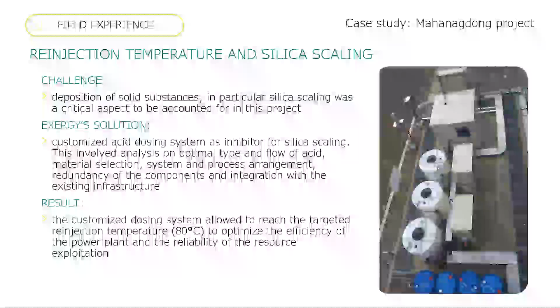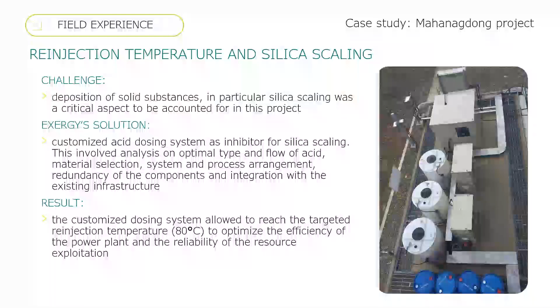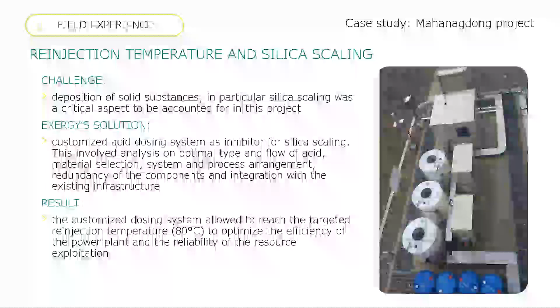So we developed a customized system for acid dosing that consists of injection of highly concentrated sulfuric acid into the brine flow. Together with monitoring of the brine pH downstream of the ORC, this allows careful control of the silica saturation point, enabling operation of the ORC cycle smoothly without silica deposition issues in the heat exchanger and brine pipelines that would be detrimental to performance. This acid dosing system is key for the performance of the plant.